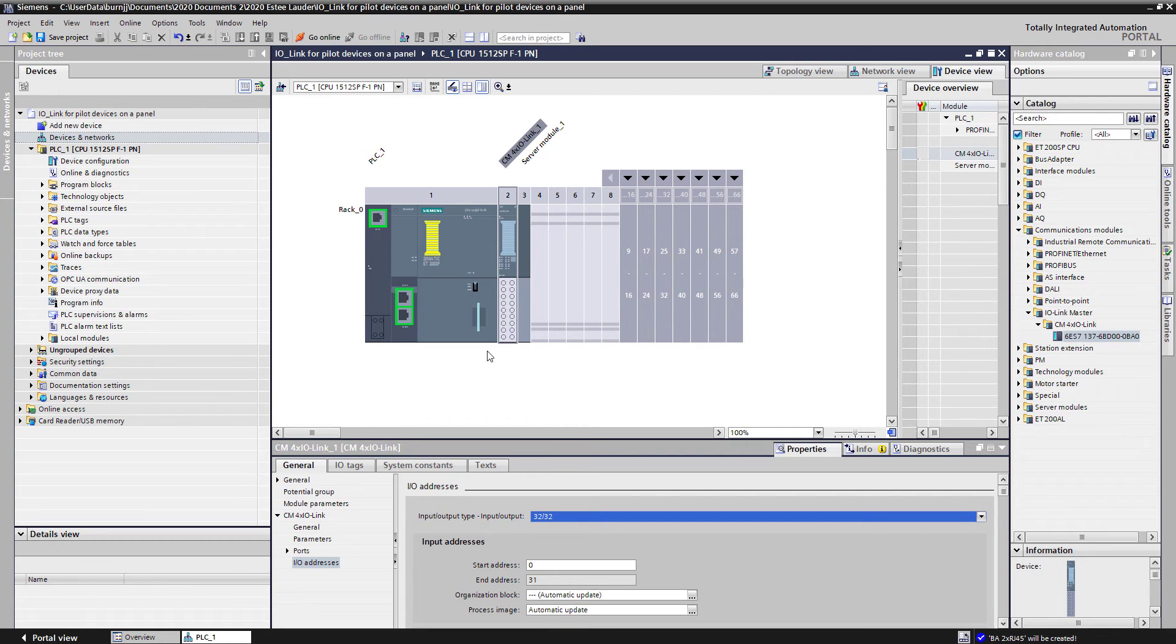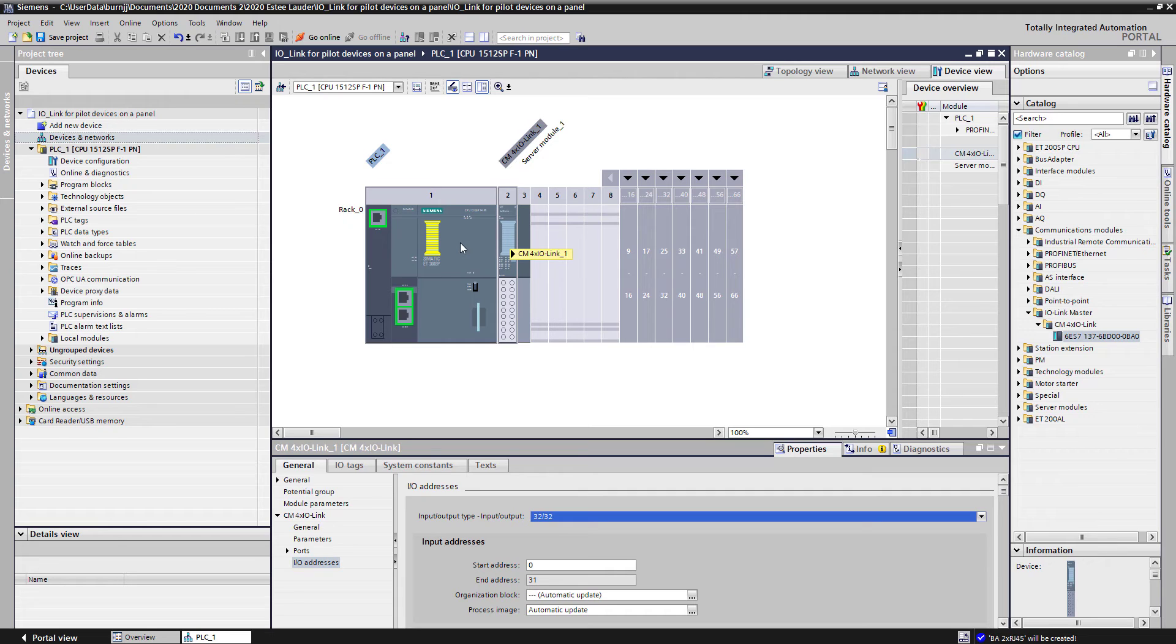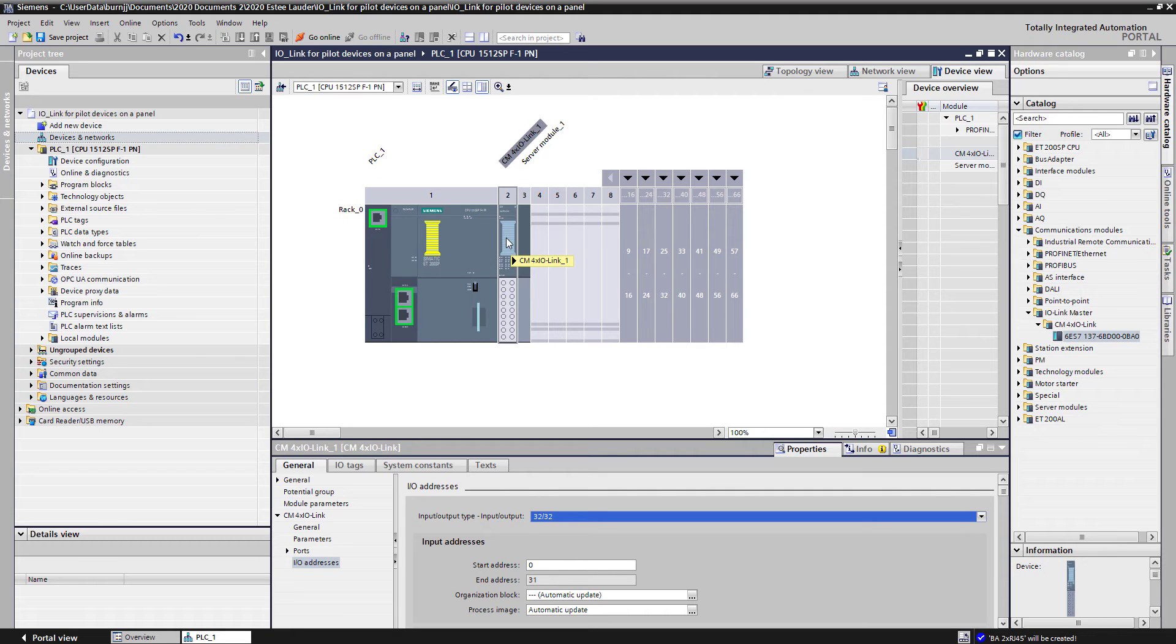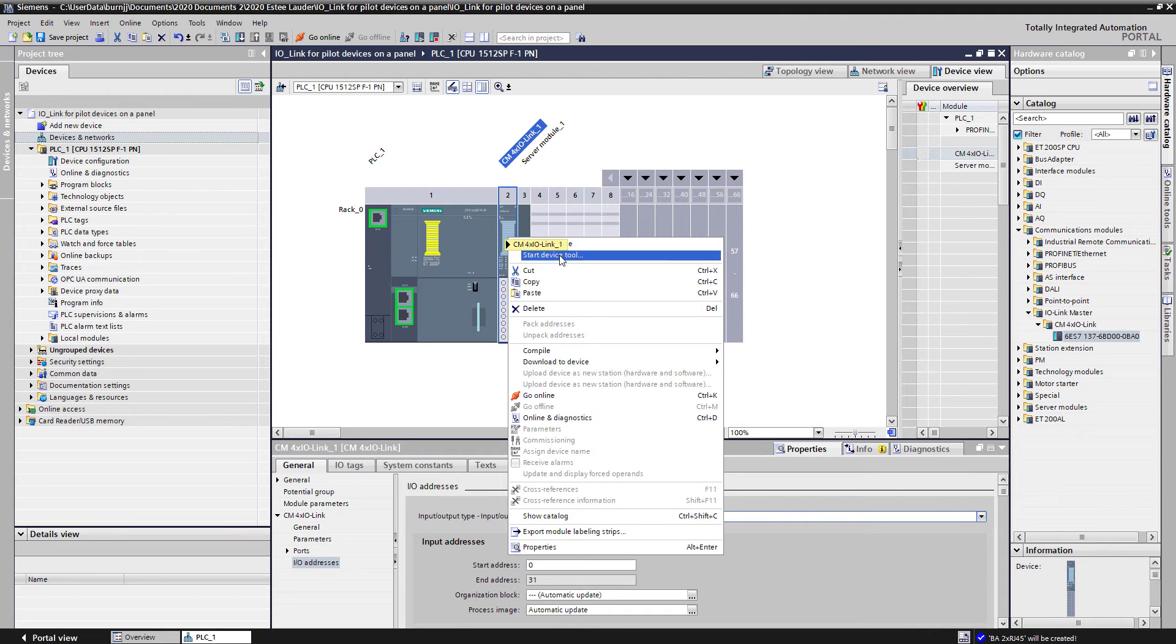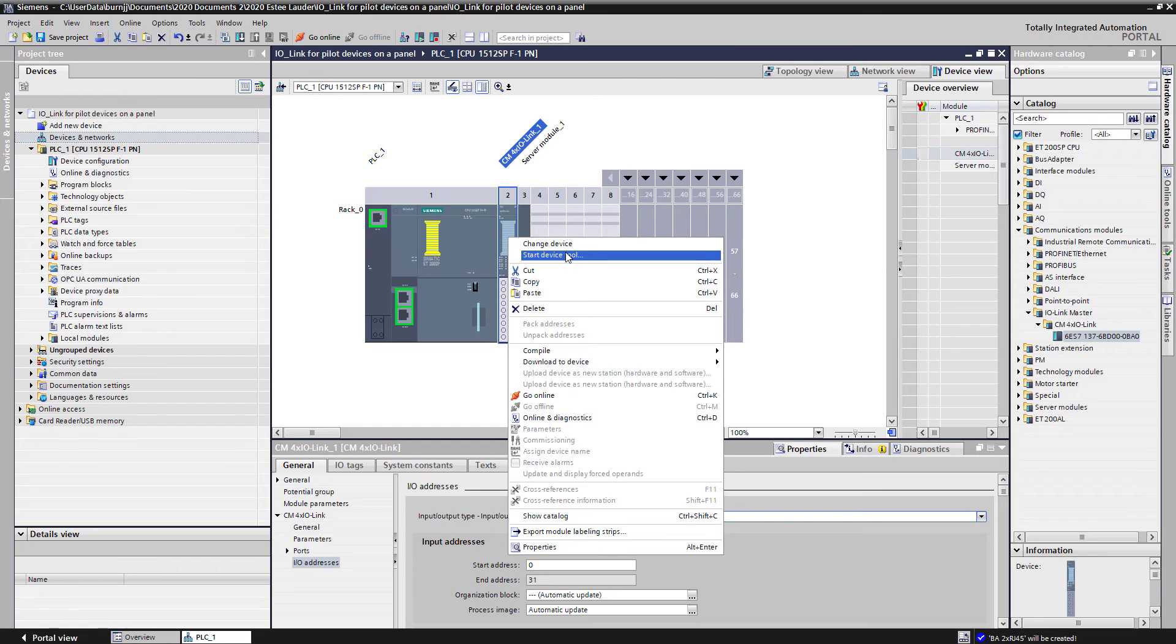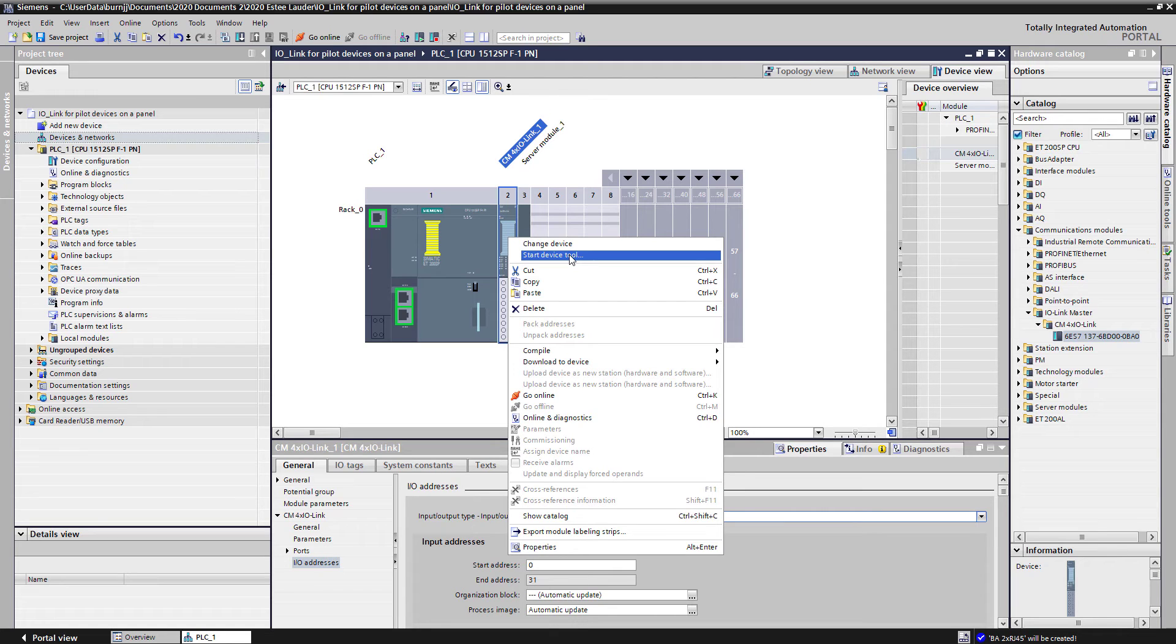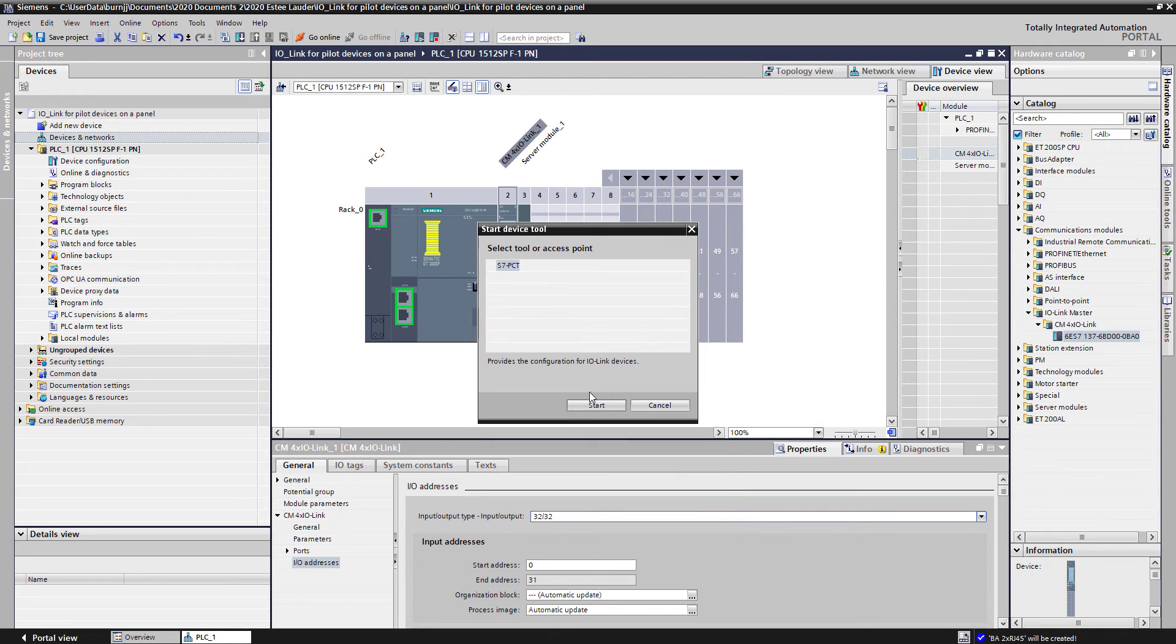Once you have that IO-Link master inserted into your rack, you want to go ahead now because the CPU will see the master, but now you have to configure the master to go see the IO-Link devices. We do that using a tool called a PCT tool or port configuration tool, and here we can start that tool. If this link is not active, that means the port configuration tool has not been loaded onto your laptop. It's a free download from our service and support website. Once it's downloaded, it integrates itself into the portal software. So I'm going to go ahead and start that tool.